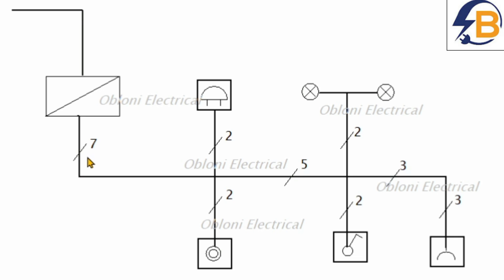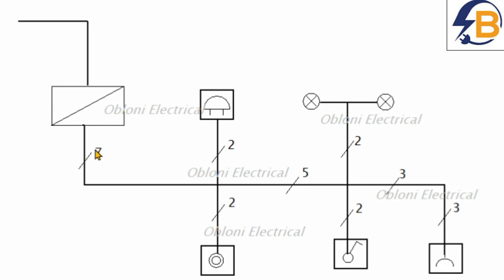Now we understand what the numbers represent. The next important thing is to identify which cables are passing through here and where they are going. We have a socket outlet here, and because this is a socket outlet we need three wires to connect to it — so three of these wires will pass through here and connect to this socket outlet. Out of seven we have three that are going to this circuit.